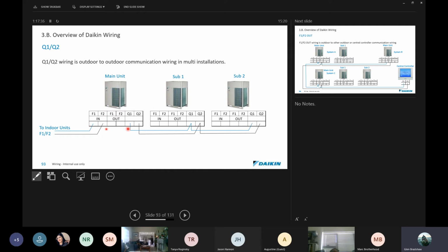You don't need to put an F1, F2 into the sub 1 and sub 2 unit, what we also call slave 1, slave 2. Don't do that. These units will now communicate, and because they are in this configuration, these 2 units will hand over their control to the master unit or the main unit.